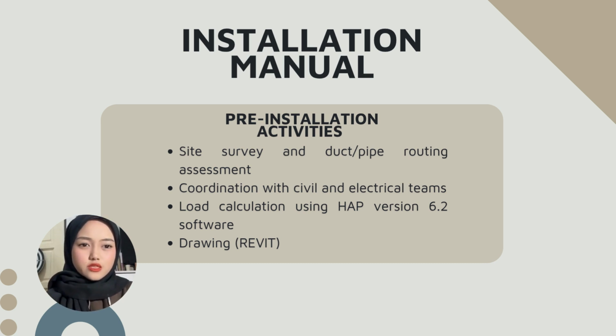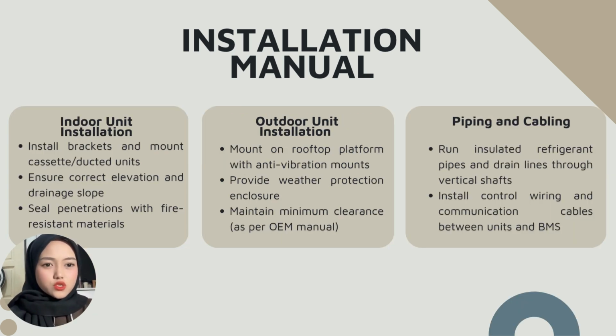For pre-installation activity, first we do a site survey and duct pipe routing assessment, and then we do coordination with civil and electrical teams. Then we do load calculation using HAP version 6.2 software. And last, we are drawing using Revit. For indoor unit installation, we install bracket and mount cassettes, ducted units. Ensure correct elevation and drainage slope. And seal penetration with fire resistant material.